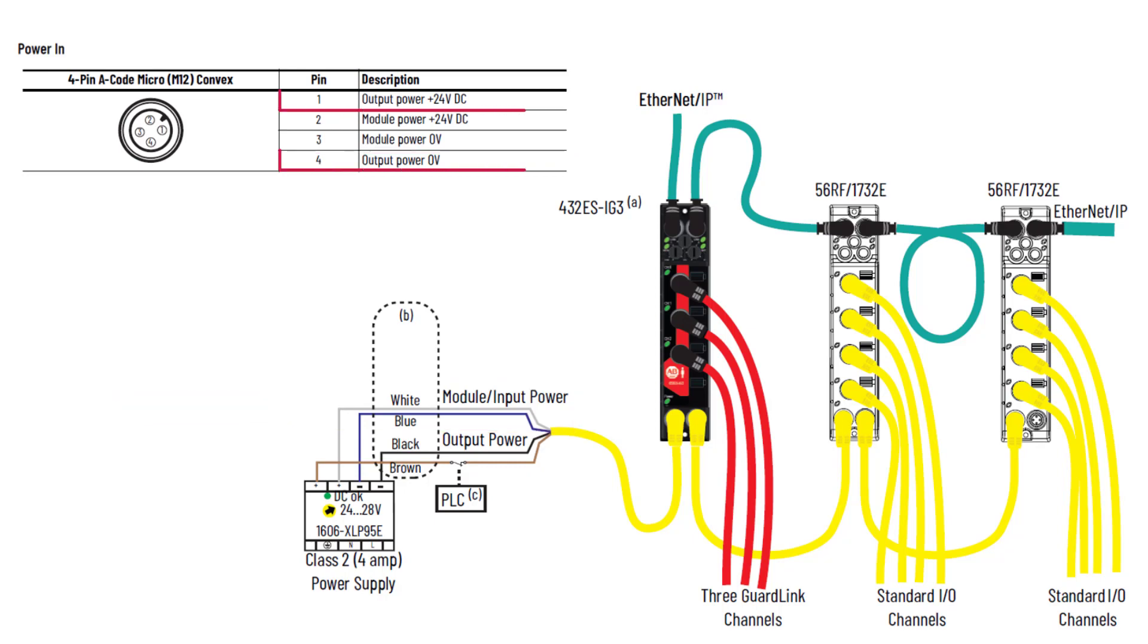The output power on pins 1 and 4, or the brown and black wire of a typical power cable, is not required for this module but passed to the next module if present. This wiring convention follows other on-machine I.O. products, but may be different from some sensor and component power cable wiring.